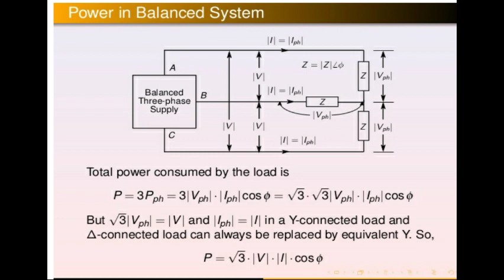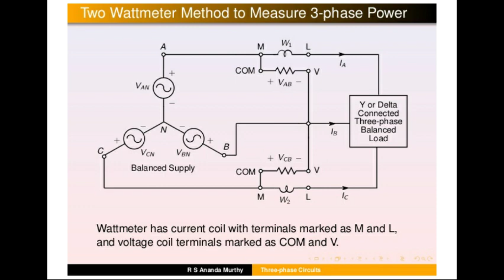Now, power measurement by the 2 wattmeter method. The 2 wattmeter method is used to measure the power in both balanced and unbalanced load conditions. The figure shows 2 wattmeters W1 and W2, whose CC is connected in series with the line and PC is connected between two lines, as shown in the figure.